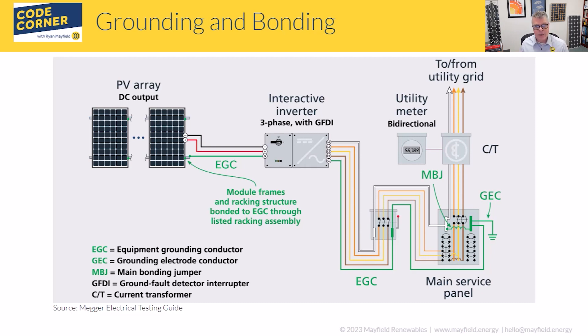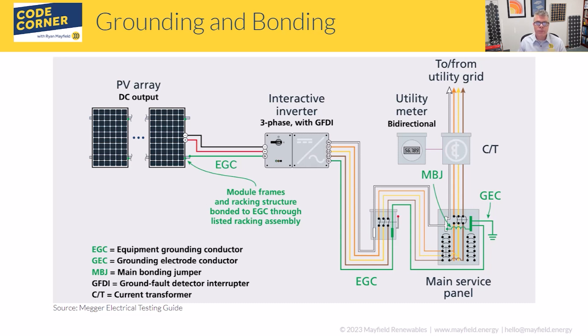Inside the main service panel there are a couple of different things to note. We have the MBJ — the main bonding jumper — which bonds the grounding electrode system to the grounded conductor, or neutral. That's the common configuration in our electrical systems here in the US. The MBJ can be wire type or other methods, and it makes the connection bonding the neutral to the earth ground.